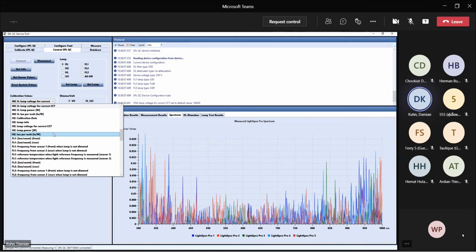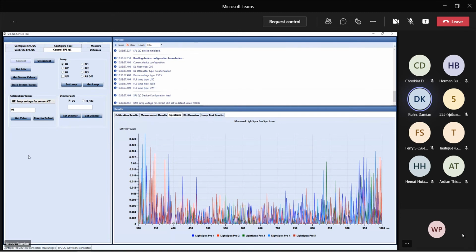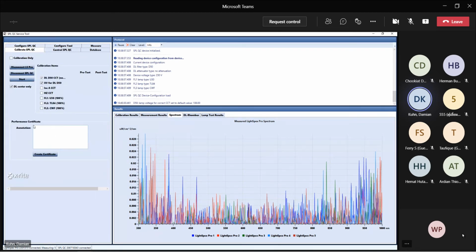And then, of course, you can do that as well for the horizon light source, where we use a different default value. Now, of course, by doing this and resetting it to default, you are actually changing the color temperature of that light source, right? Because you changed the lamp voltage. So whenever you do that, you should go back to the calibrate SPLQC tab and select those light sources where you set the lamp voltage back to default, in order for these light sources to perform as expected in terms of color temperature. So those were really the changes we did to the software.